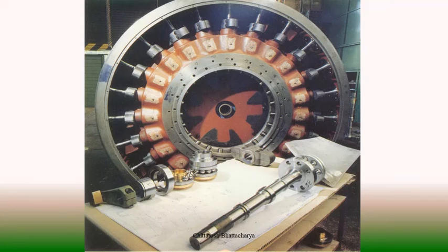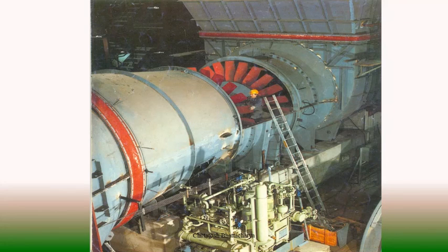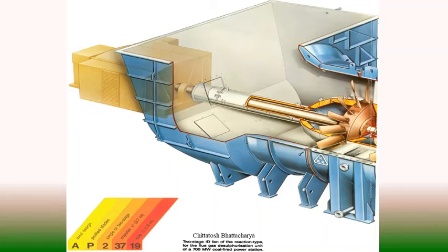axial blade pitch control, and you see these blades are placed in such a way that they are totally fitted in the hub and can tilt with respect to the impeller hub without getting any leakage of control oil or without affecting the flow beyond the limits.